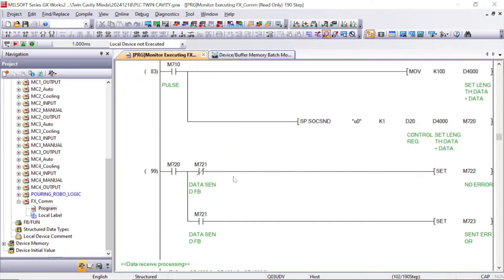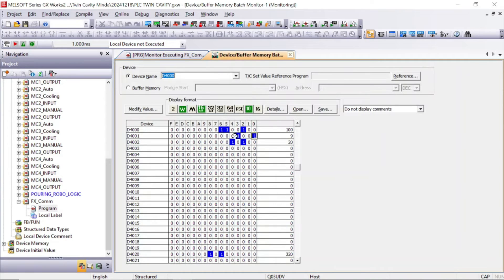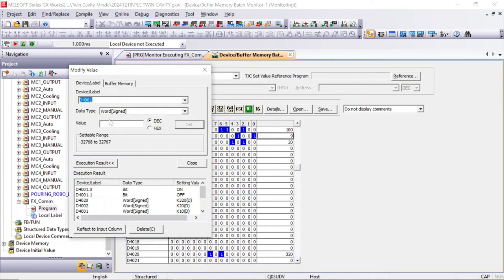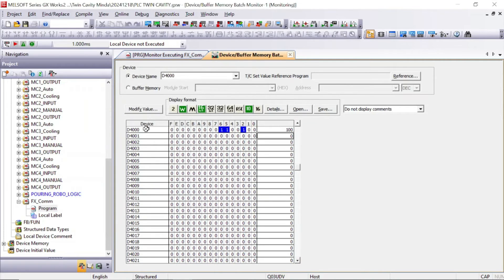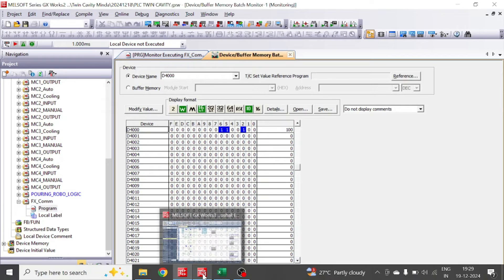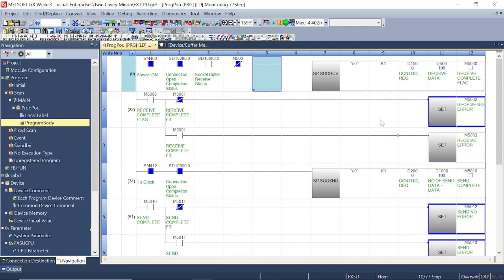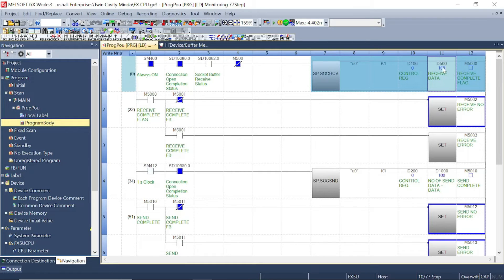In Q series, we will write data in D4000, so let's monitor D4000 here. From D4000 to D4099, this data will move to the FX5U PLC in D500. We are receiving data in D500, so let's check D500 in the FX5U PLC.